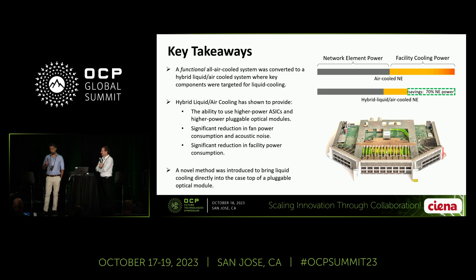Question: Could you compare your approach to pure immersion cooling in terms of performance? That's a good question, but it depends — it boils down to infrastructure, whether it's available and doable. We chose this hybrid approach because we thought it would be a middle step toward perhaps immersion cooling in the future, but to start with, we think the hybrid liquid-air system is good at least for optical networking equipment. The other challenge with immersion is we are not 100% sure how the optics behave in an immersion environment, and there needs to be a lot of testing to figure out how these optics will behave when the ambient is different. That's the big challenge for optical networking with immersion cooling.